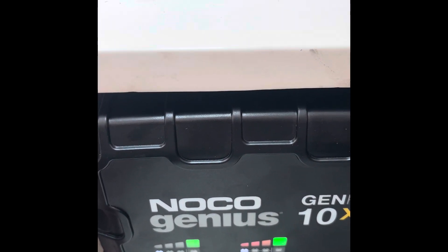All right, so we got the new charger installed. A nice thing about these — you click this button here to select which battery type: AGM, lithium-ion, or you can turn it off. Click here and that's going to be for flooded regular batteries, your old-school batteries. That's what we got both of them set on because this boat has lead acid batteries, so that's what we're going to leave it on.